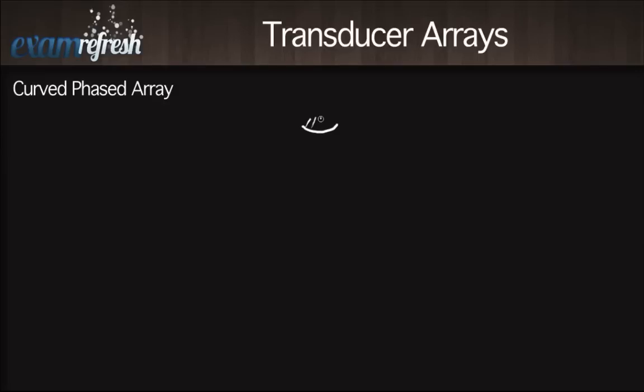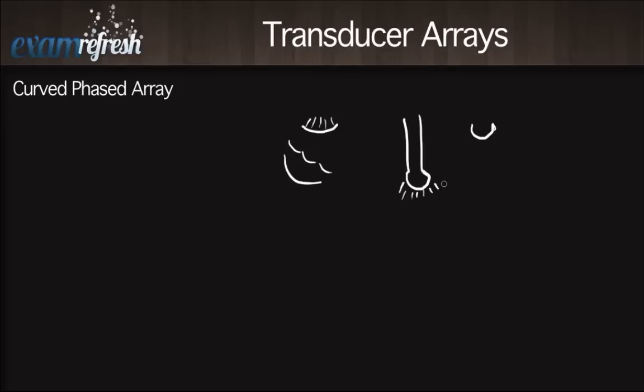The curved phased array, like the linear phased array, has a small footprint and a few crystals that fire in phases. We most often see this type on small pediatric probes where a small footprint is needed to fit between tiny ribs, or on transvaginal probes — which are long with a small curved face — creating each section of the image one phase at a time.